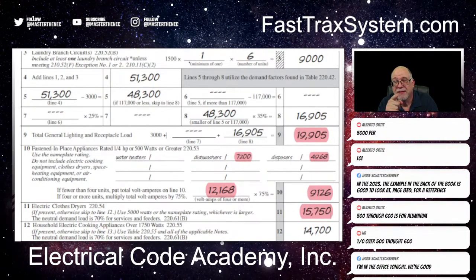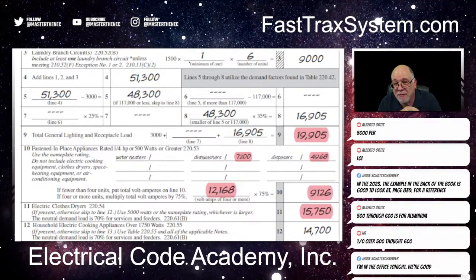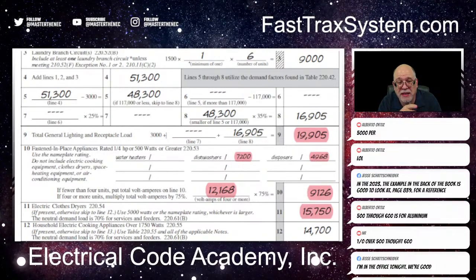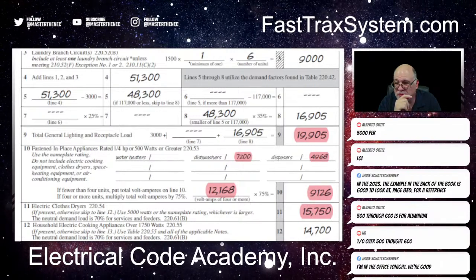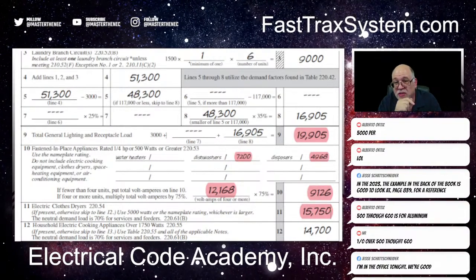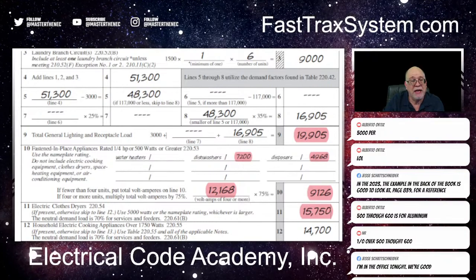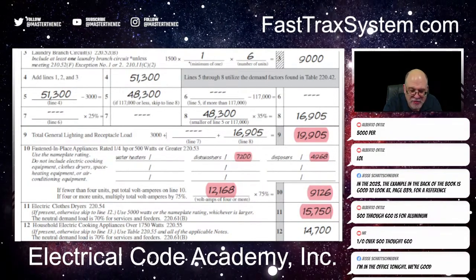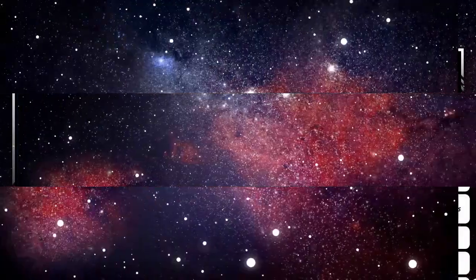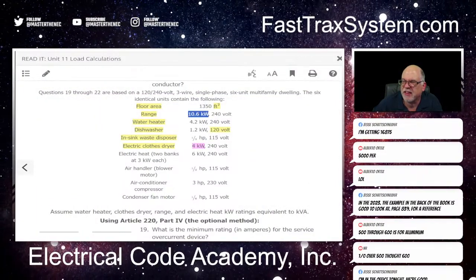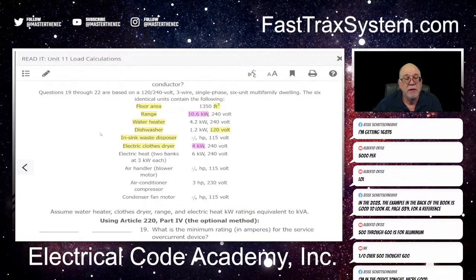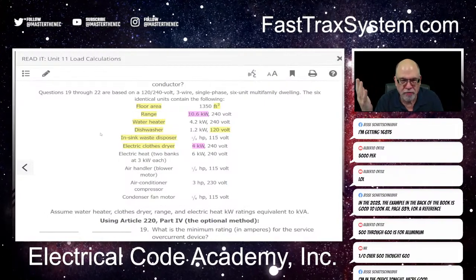All right. Now that you did that, you ought to know how to do the range application here. Let's see how this works for the household cooking appliances on this standard method. Okay? All right, so let's go look. So how many do we have? We have 6. Now, in our calculation, let's go to the NEC. Oh, no, let's go to the lesson. Yeah, so in our lesson, we have 10.6 kW range, okay? All right, now, it's not over 12. Okay.